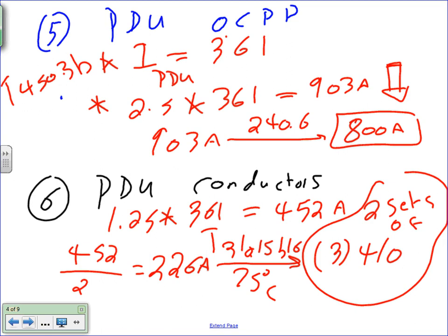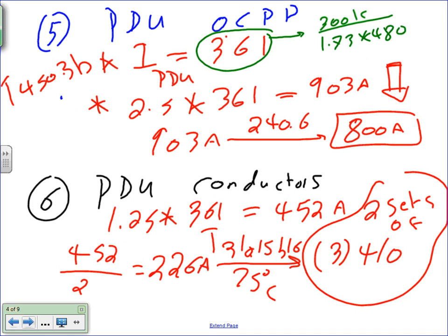Ken, where did you get the 361? 361 is the amp, guys, for the PDUs, which is the same as the amp for the UPS, the same size. The UPS was 300 divided by the voltage. This is the amp for the PDU on the primary side. This is coming, guys, from 300 kVA divided by 1.73 times 480. Cool? Can you write this? Because if you take 300 kVA divided by 1.73 times 480, that gets you 361. Based on the 361, you size the conductor and the overcurrent protection device on the primary side.